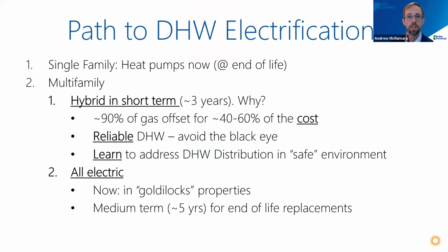For multifamily central systems, I'd encourage us to facilitate hybrid installations, particularly over the next 3 years. The reason is that we can get 90% of the gas offset, 90% of the carbon reduction, for about 40 to 60% of the cost, and we can do so reliably, so we don't give the technology a black eye. Really, every one of our installations to date has brought new lessons learned, and it was so valuable to have a safe place to work through those lessons.